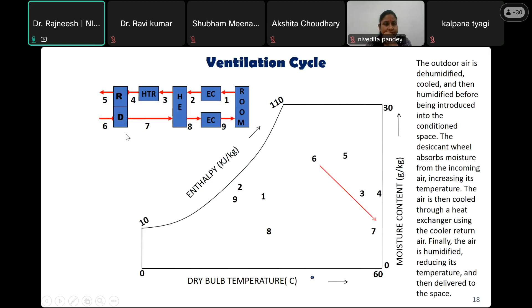So this is a desiccant wheel. The above half portion acts as a regenerator, and the lower half portion acts as a dehumidifier. Air is supplied at this point, point 6. We'll understand this process on the psychrometric chart in parallel. So air is being supplied to the desiccant wheel. What the desiccant wheel does is remove the moisture from the atmospheric air, which, like in the rainy season, has more humidity. So we feel too uncomfortable.